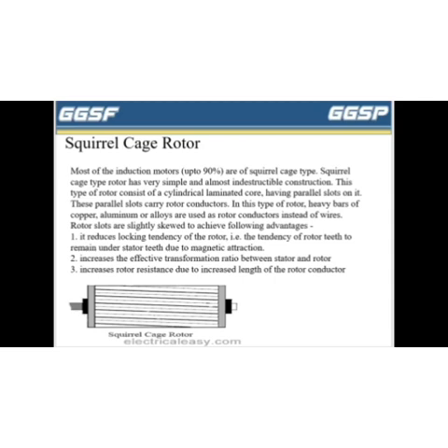Rotor slots are slightly skewed to achieve the following advantages. First, it reduces the locking tendency of the rotor, that is, the tendency of rotor teeth to remain under stator teeth due to magnetic attraction. Second, it increases the effective transformation ratio between stator and rotor. Third, it increases rotor resistance due to the increased length of the rotor conductor.